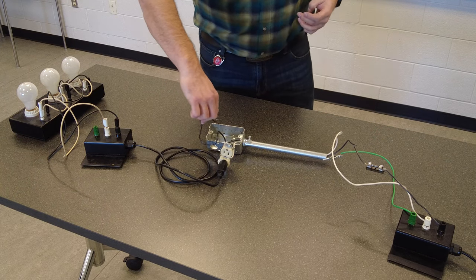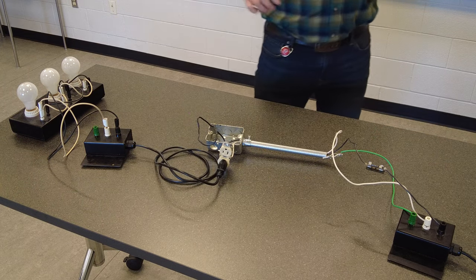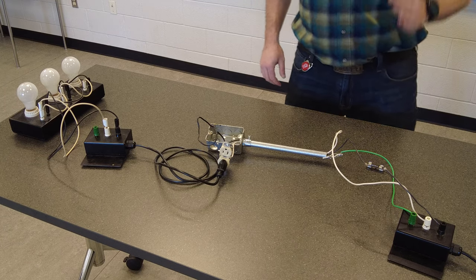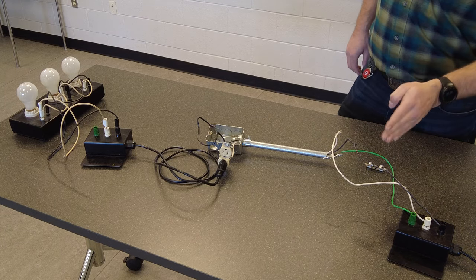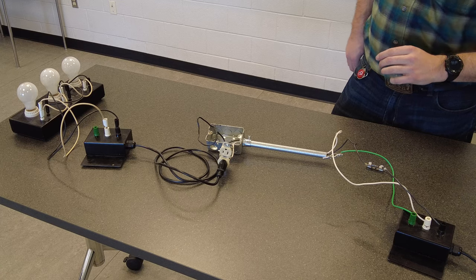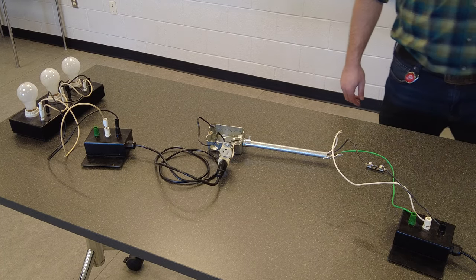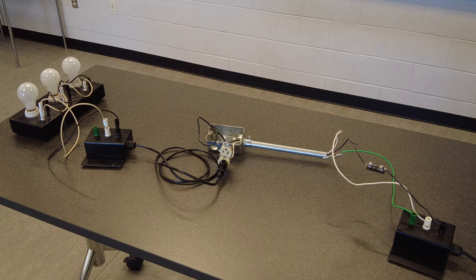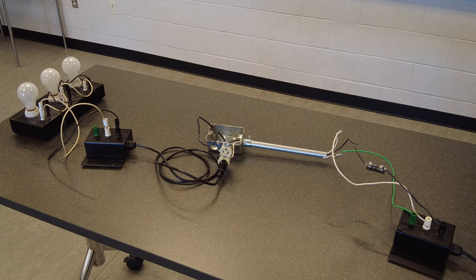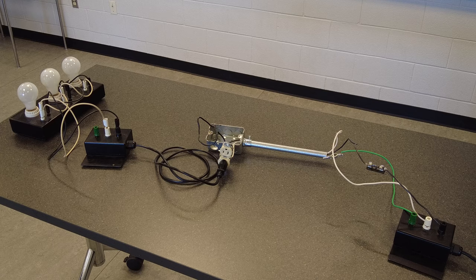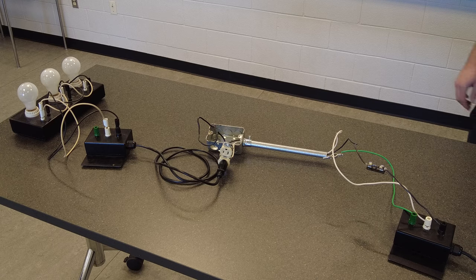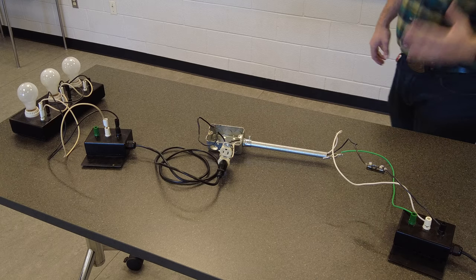Right? That low impedance path created a large amount of current. That large amount of current popped the fuse inside or popped the little trip wire inside this fuse. So that was with the bonding connection established. Remember, that's what we want to happen. Again, that's ideal. When that overcurrent trips, that is ensuring or that's proving that our bonding is established throughout our electrical system.